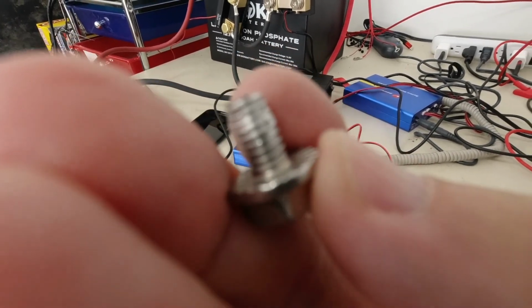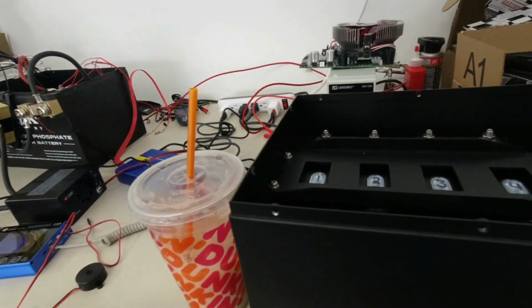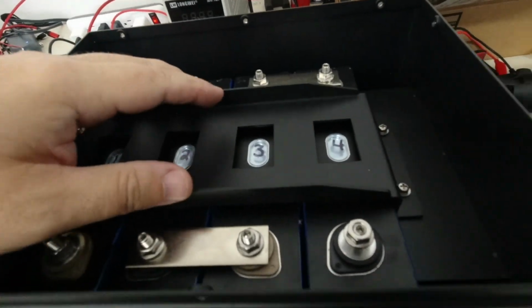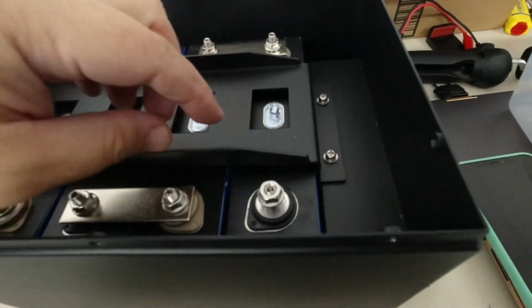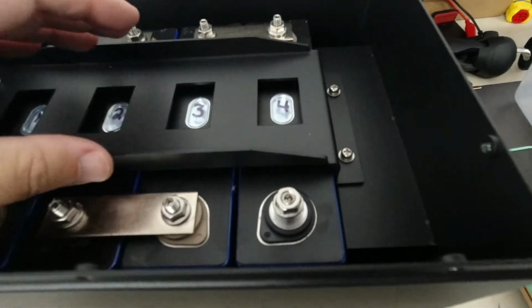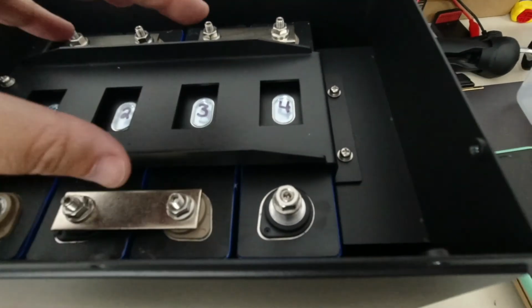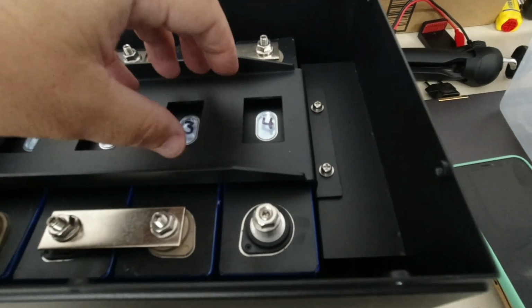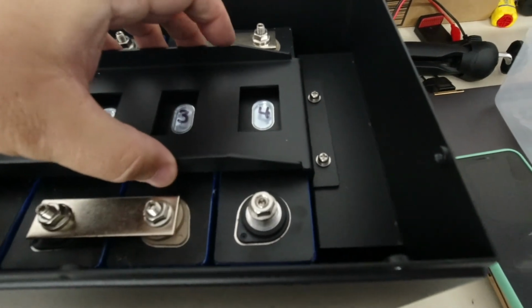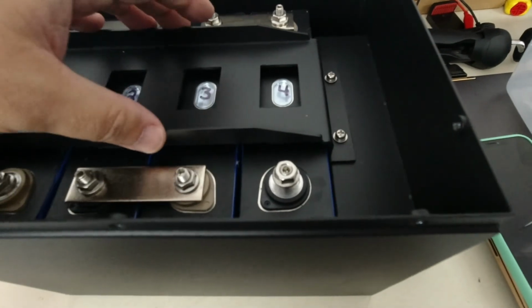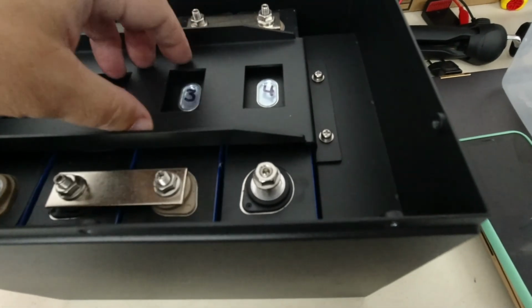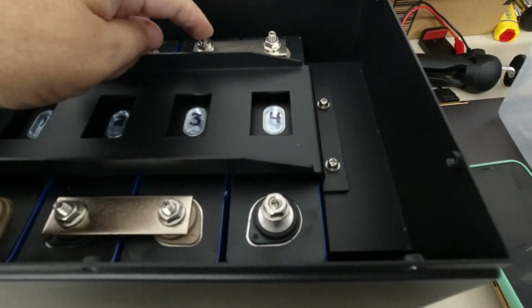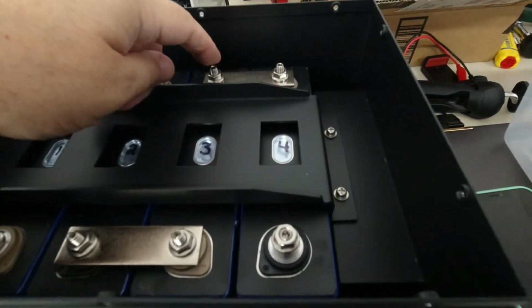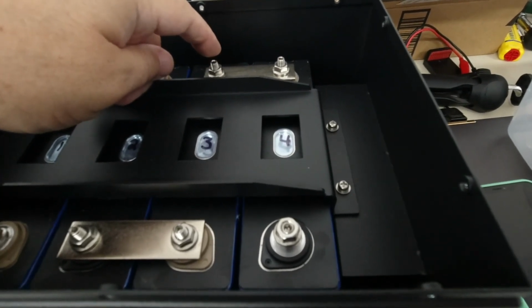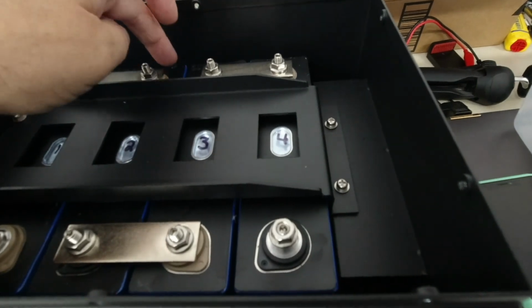It was not possible to hand tighten these bolts in. Even on this battery, all I did was remove the old bolts, and then I tried to hand tighten them, and I couldn't. So even just putting in the bolt once, the way they're doing it isn't going deep enough, or it's over torqued. Whatever the case is, you should always be able to hand tighten the bolt, or in this case the stud, all the way down. If not, then that means the threads have been warped or damaged or some such.